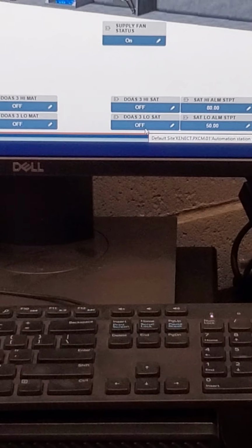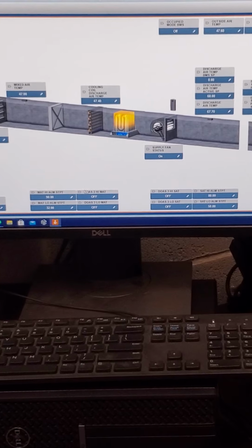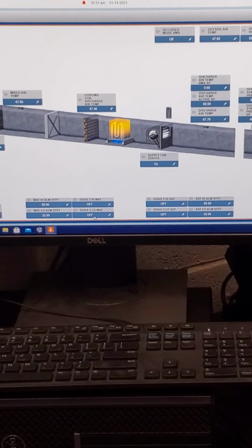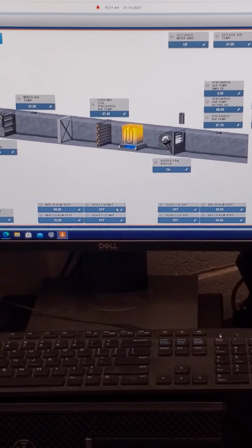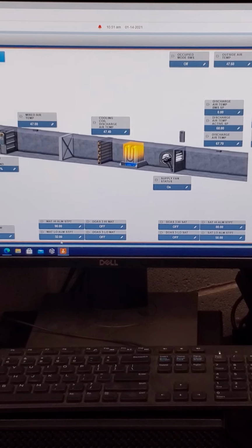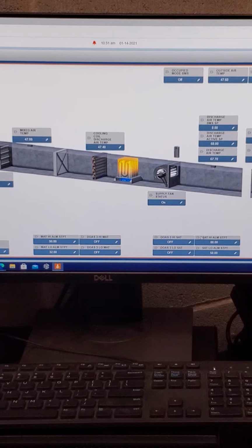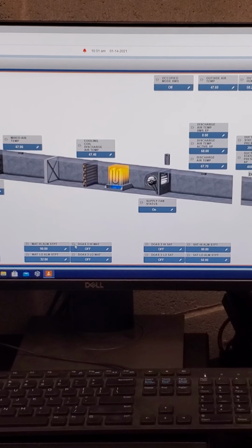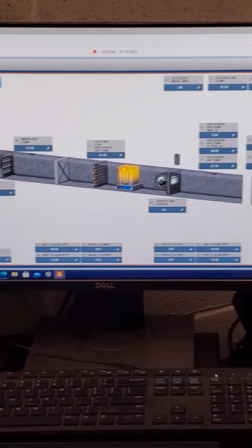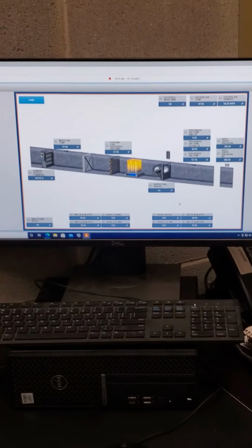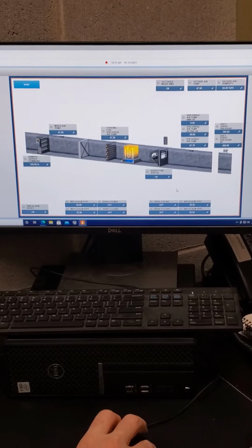But we have a high and low alarm that'll trigger. If either of those are active, it will generate an alarm in the alarm screen. It'll also show you on this graphic here, and also the same on the mixed air side. So I just generated 2 separate points, and you can see your levels. And it's the same layout on all 3 graphics. You don't really need to do anything here. It's just more of an indication. Once the set points are where they need to be, if the alarms pop in, you'll know that that's what's going on there.